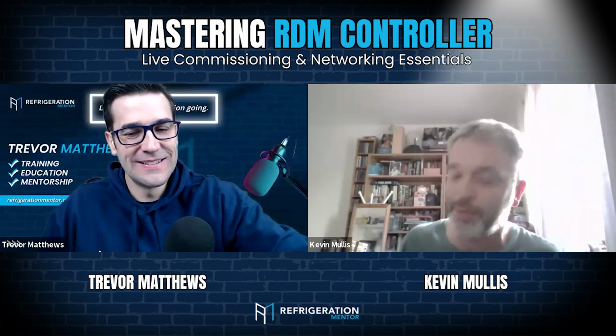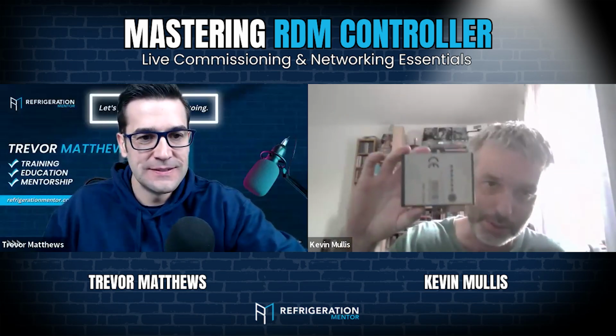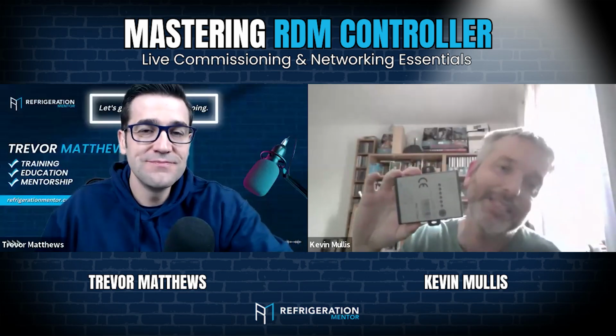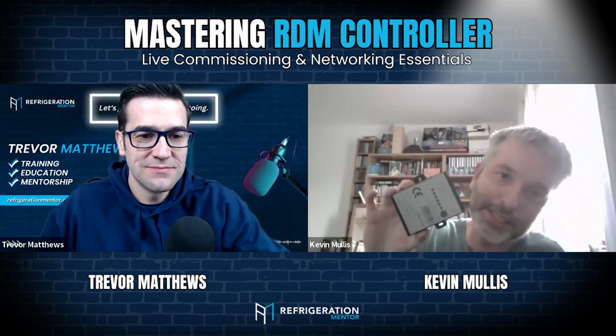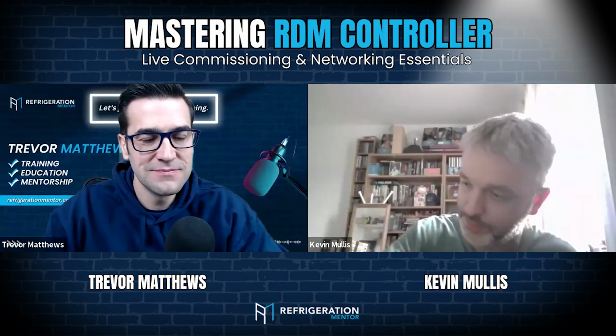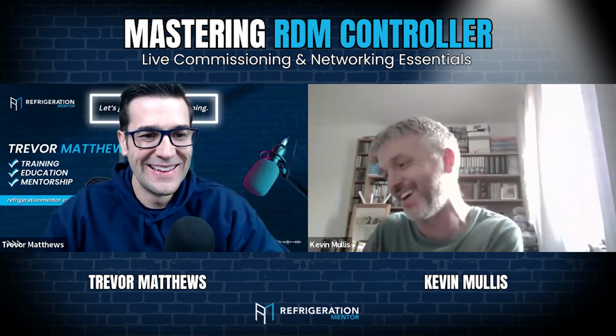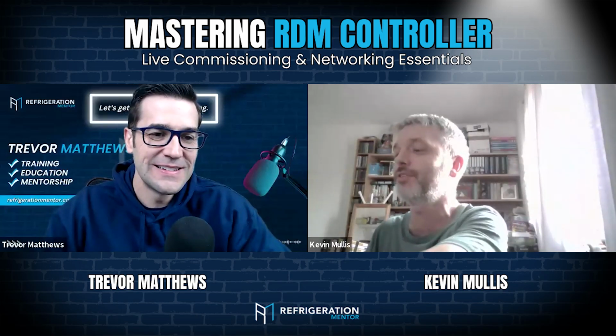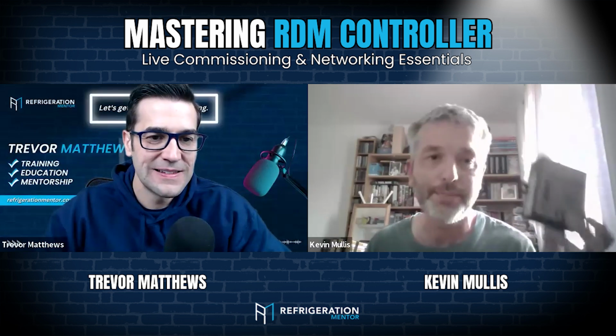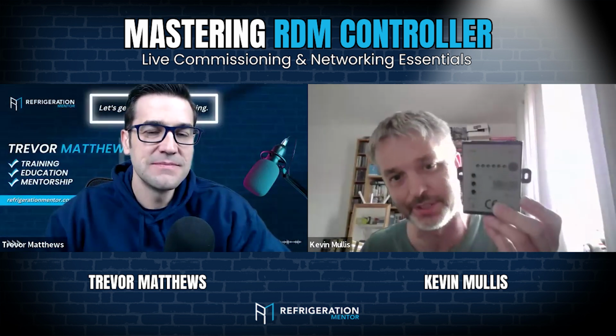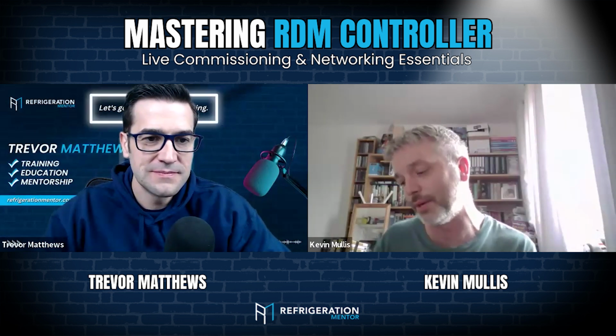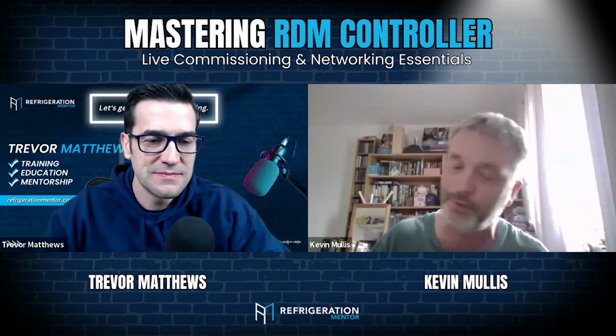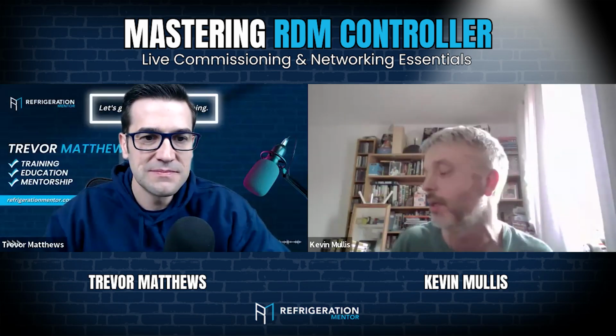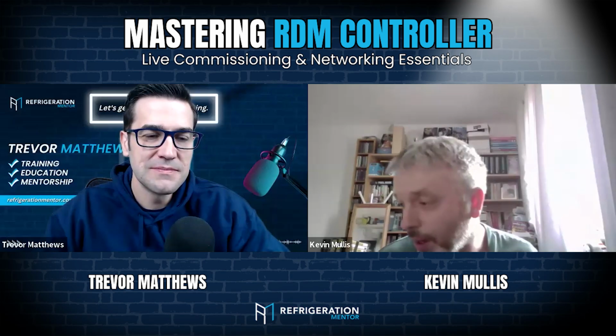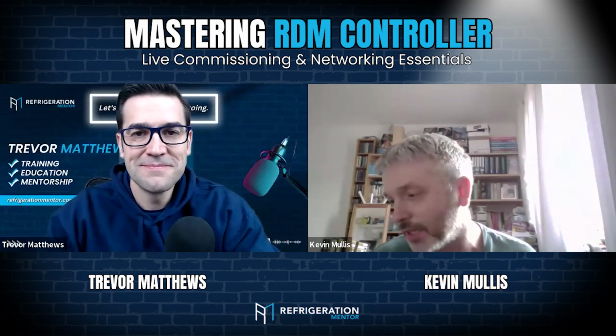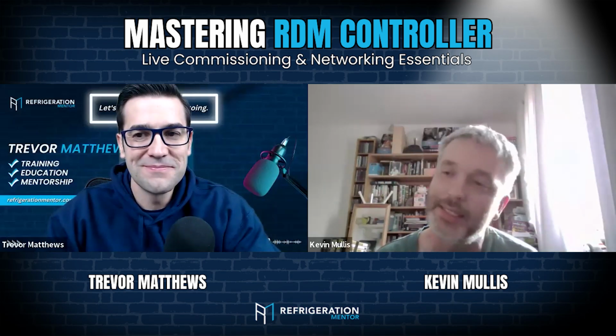If it's 232 and you want to put it on an old 485 network, they do a module to convert the standard. It's a translator. It might be green. It might look like this. This is about 100 years old out of my garage, as many of my things are. If it's a 232 controller, you can still use it on IP with a slightly different module that converts it to IP. And that was the way we used to do it, everything on RDM, before they put direct IP into the controllers. So you have options, but just because it's the right type of cable doesn't mean it's IP.